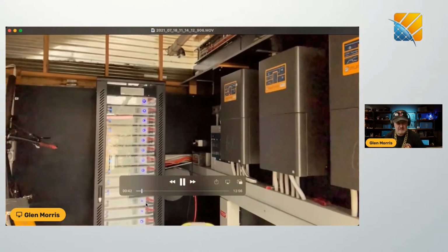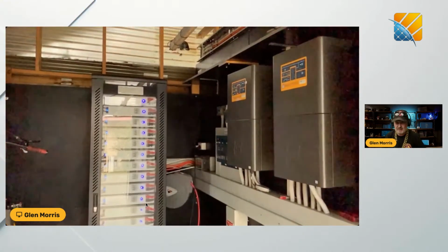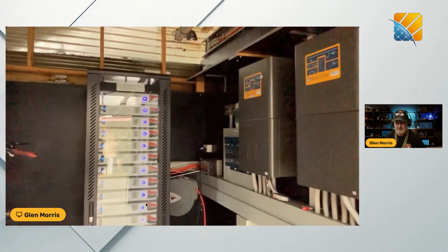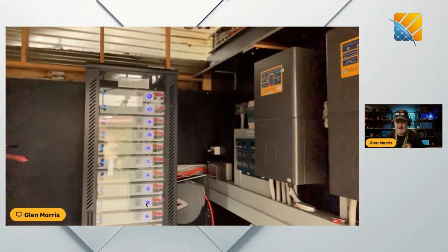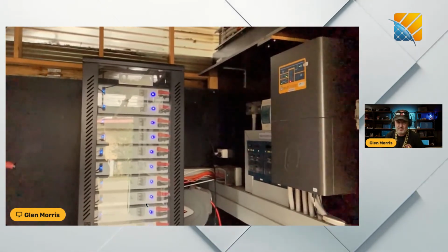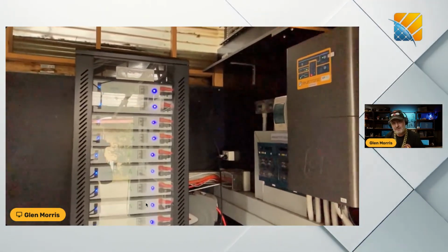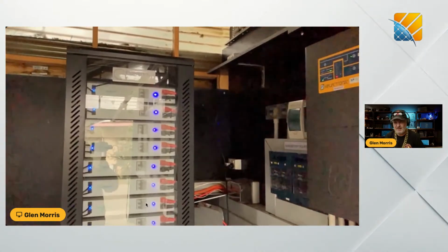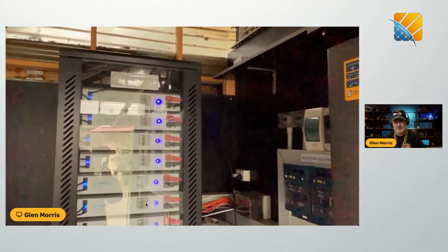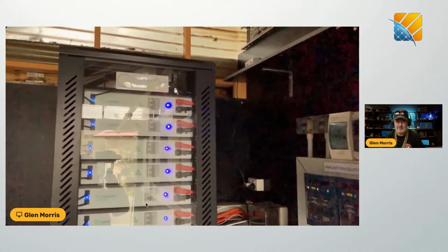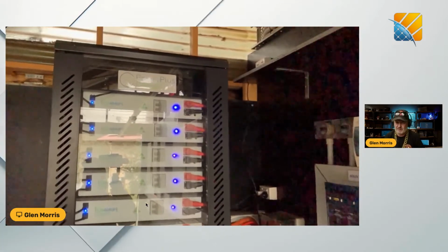One nice thing about these batteries is they have an inbuilt circuit breaker on the front, rated for load break, and it can be locked in the off position, so it meets all the requirements of isolation. You don't actually need a single isolator for the whole system — you can isolate through multiple points as long as they're in the shutdown procedure.